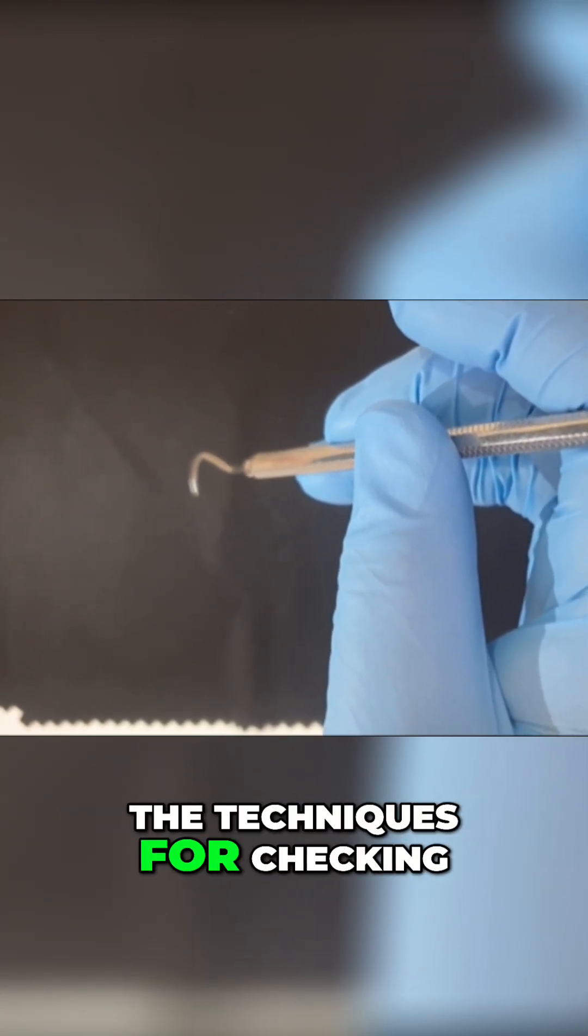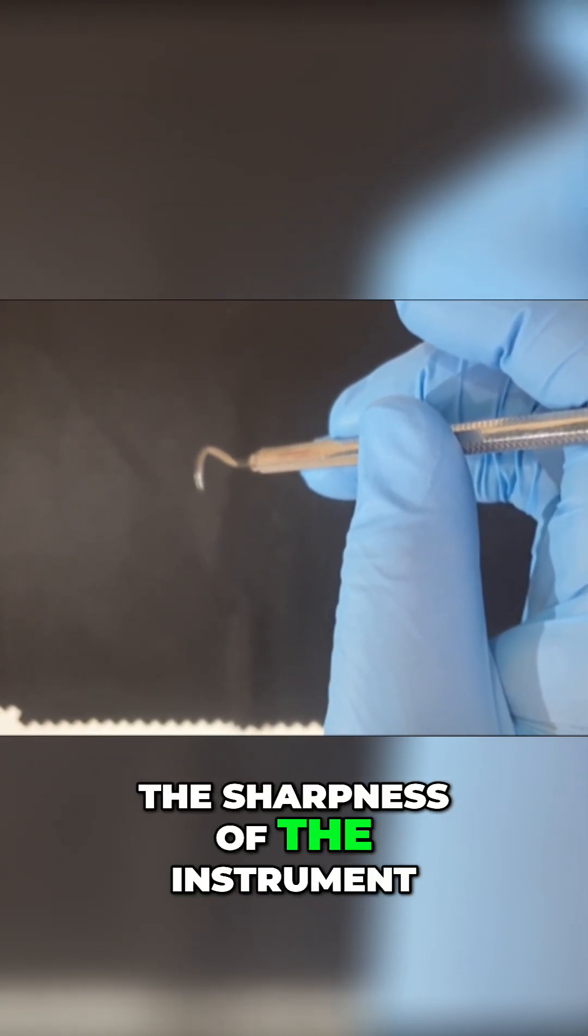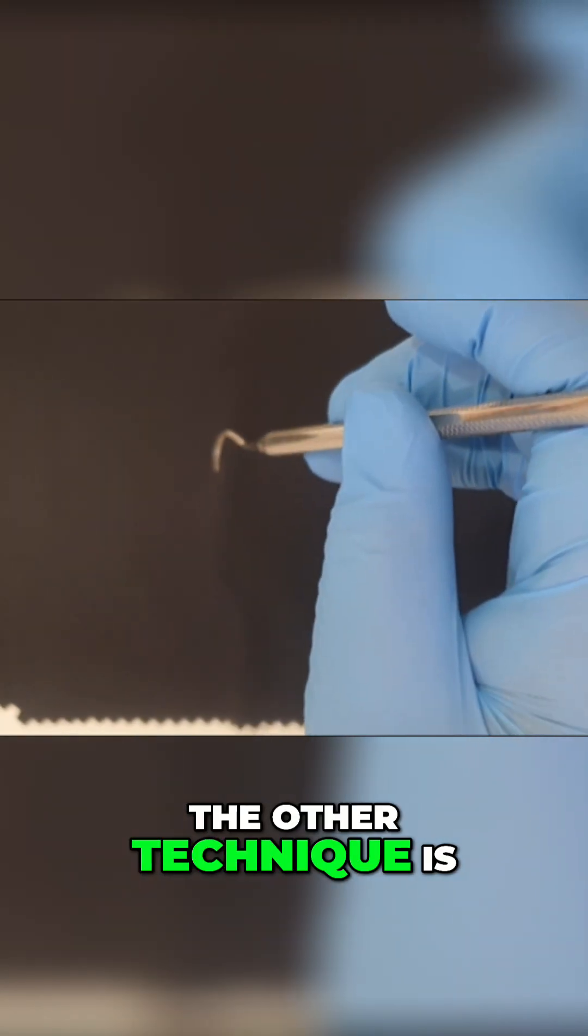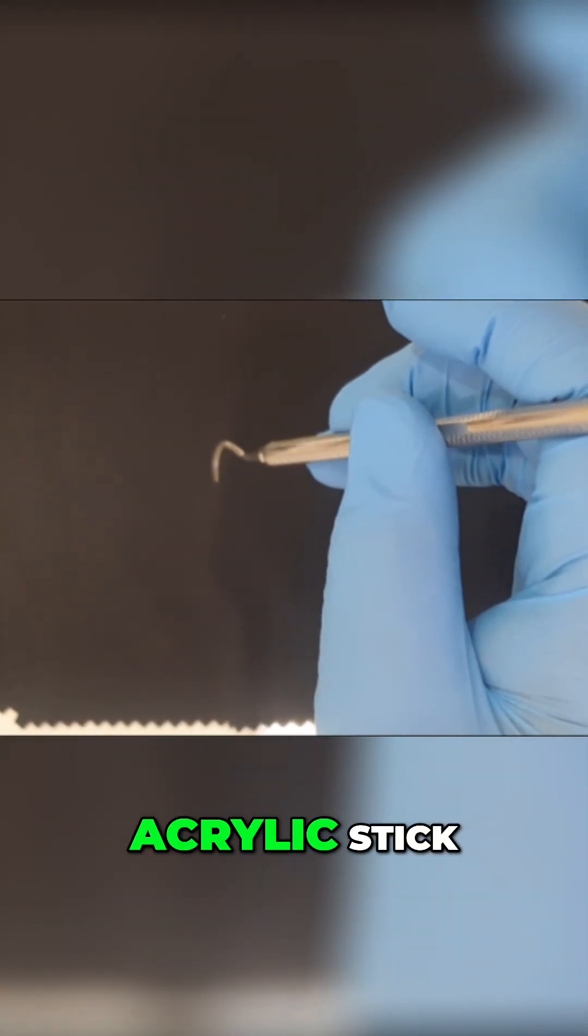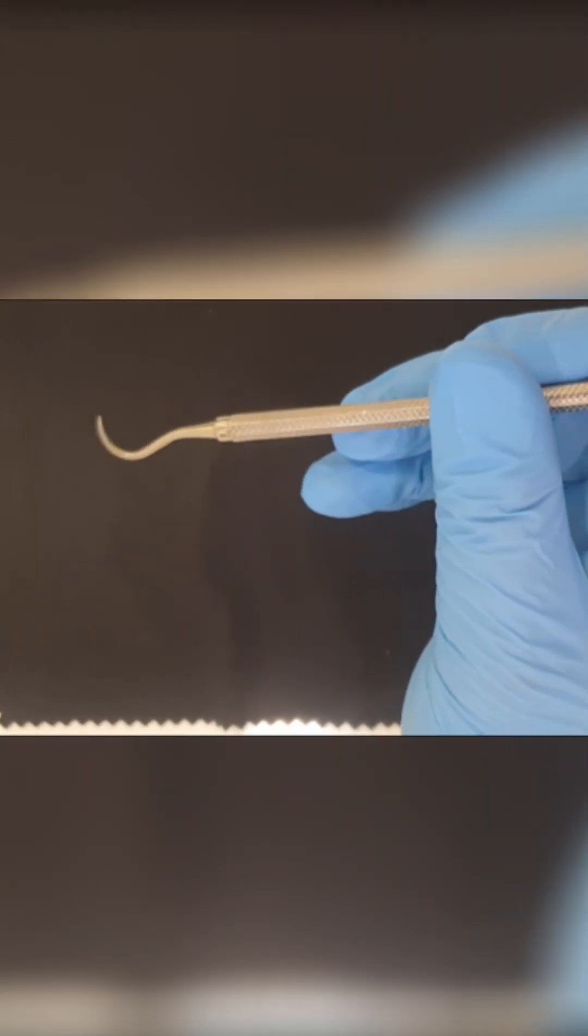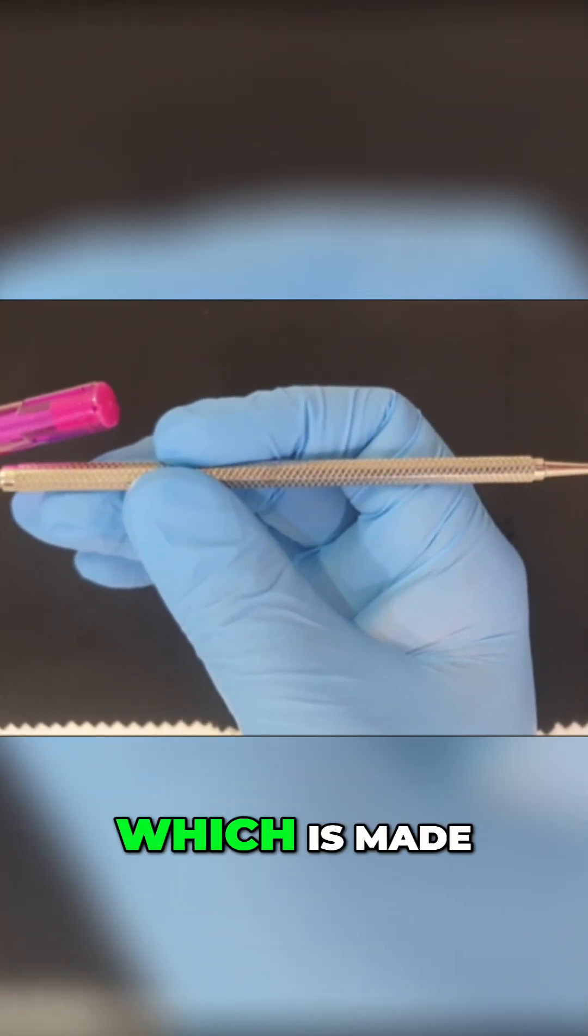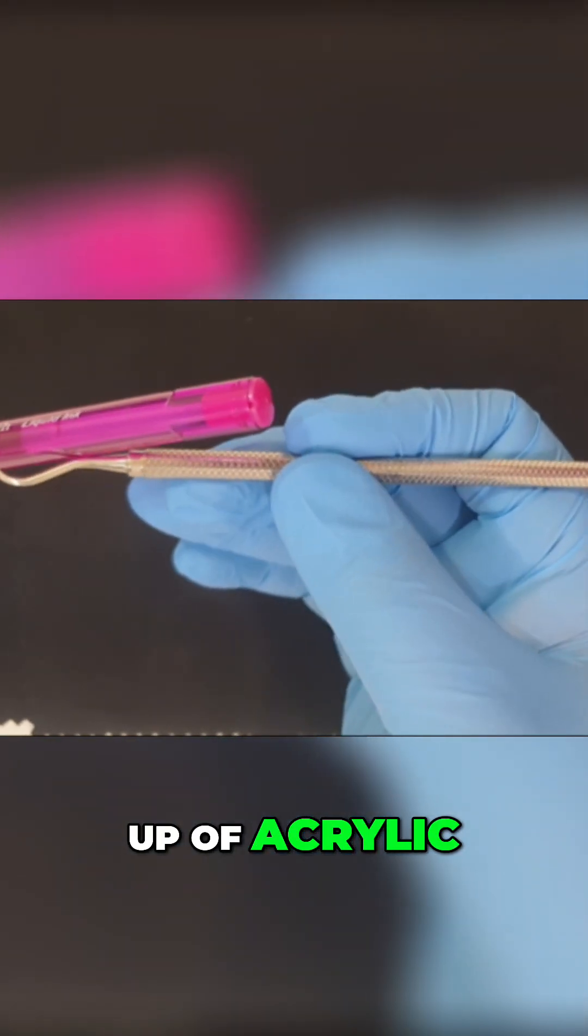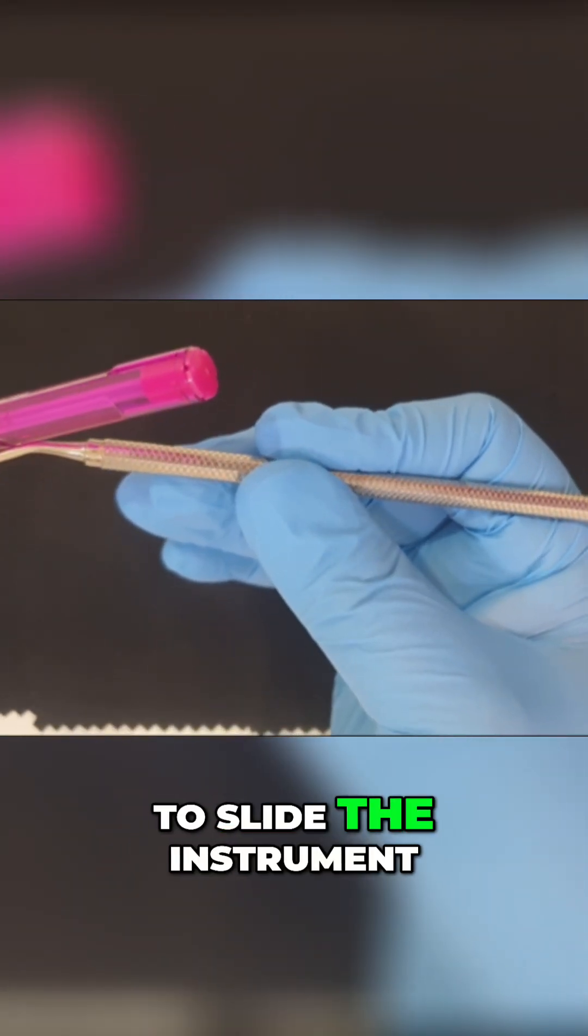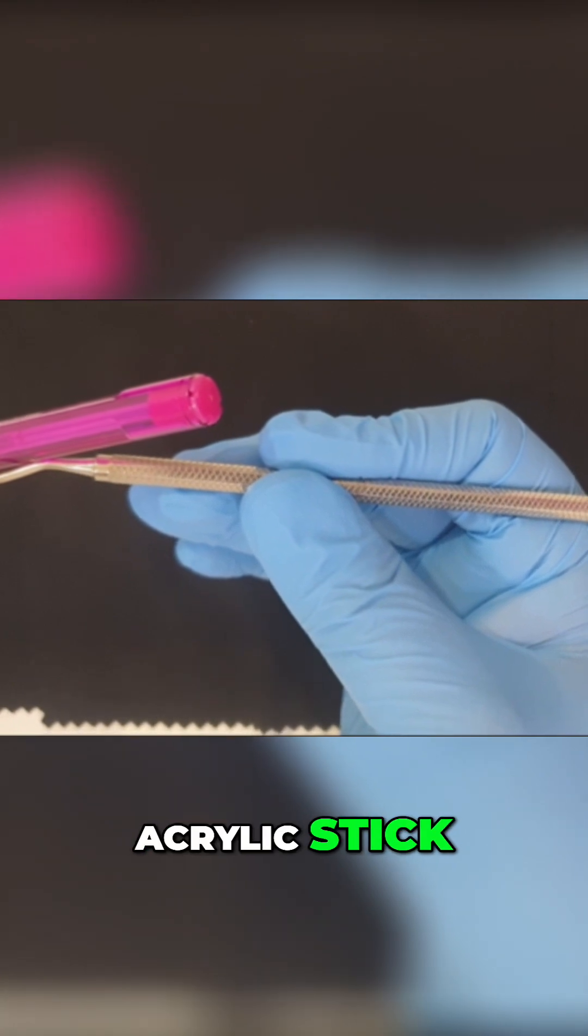This is one technique for checking the sharpness of the instrument. The other technique is you can use an acrylic stick. Since I don't have any acrylic stick, I am using this pen, which is made of acrylic.